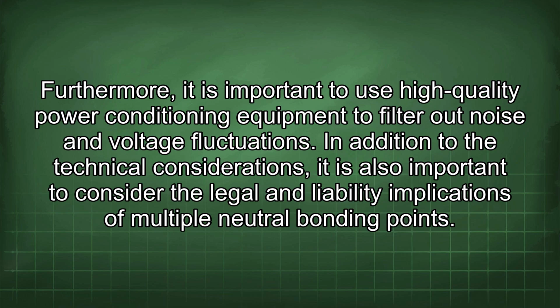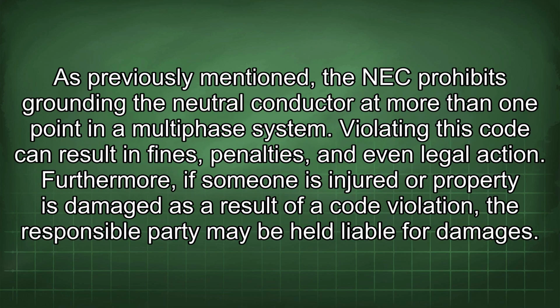In addition to the technical considerations, it is also important to consider the legal and liability implications of multiple neutral bonding points. As previously mentioned, the NEC prohibits grounding the neutral conductor at more than one point in a multiphase system. Violating this code can result in fines, penalties, and even legal action. Furthermore, if someone is injured or property is damaged as a result of a code violation, the responsible party may be held liable for damages.